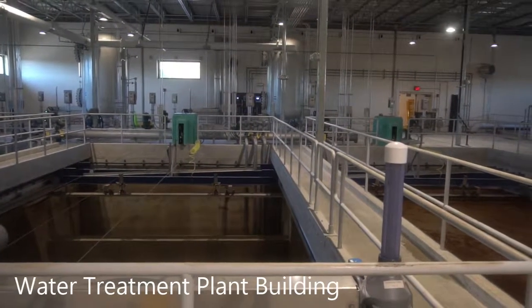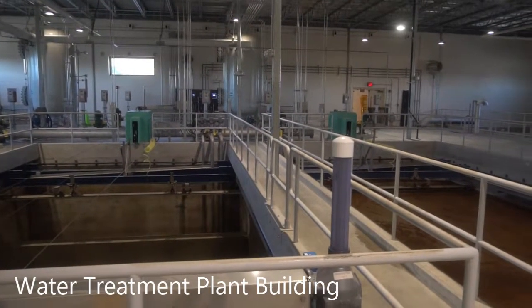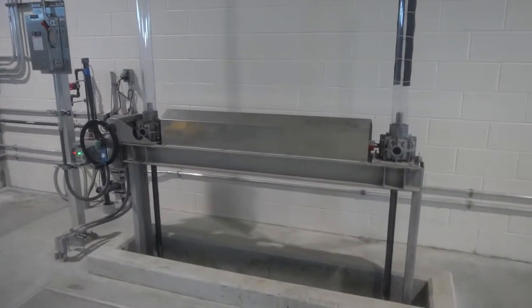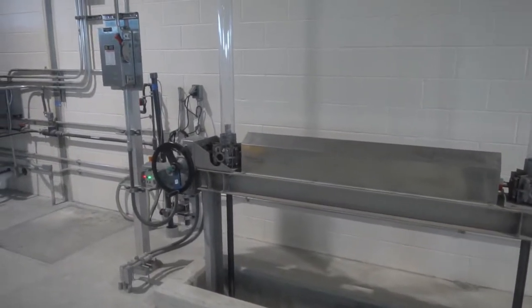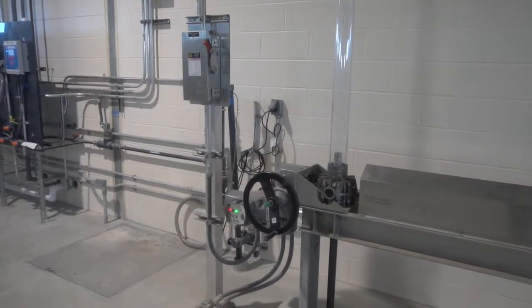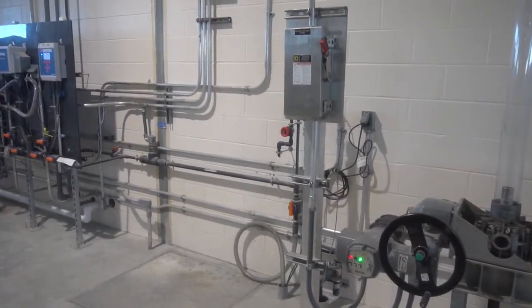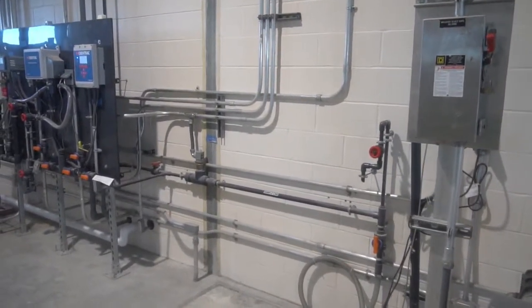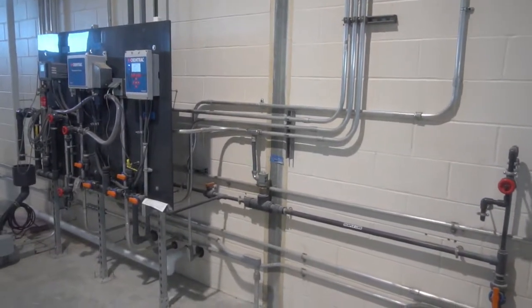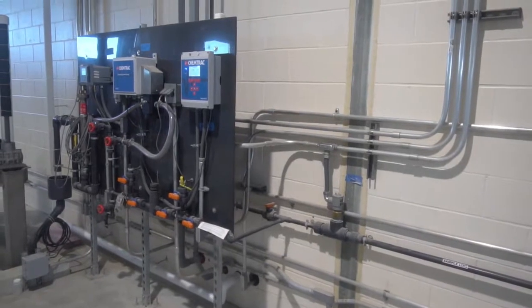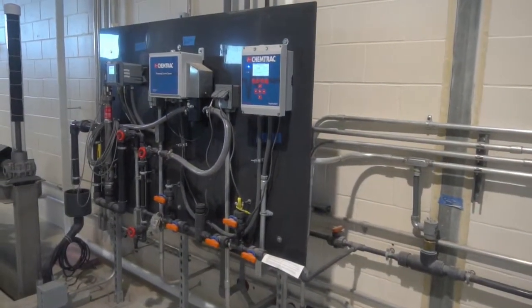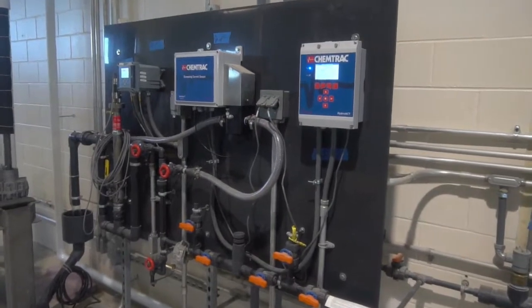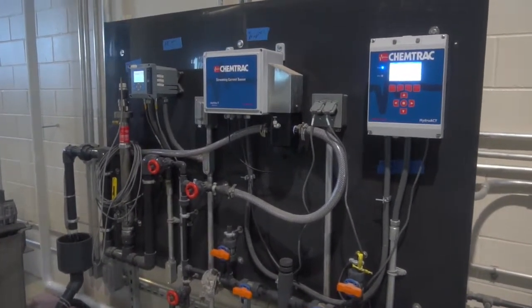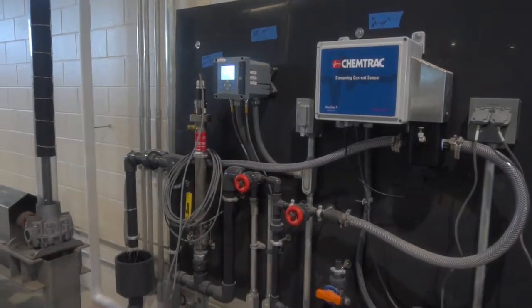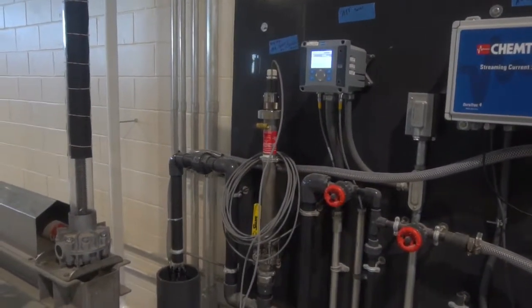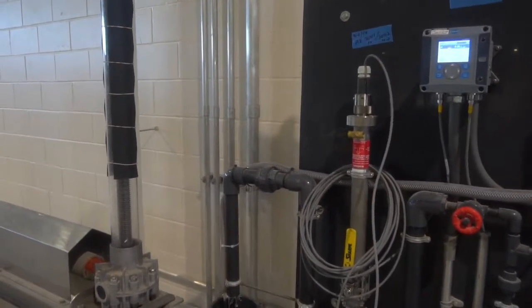We are now in the new water treatment plant facility. We installed 2 transmission lines from that low lift station which you saw previously. And they enter the building here. Paired with that equipment, we have process control equipment where we monitor the coagulation process and we monitor pH and temperature as well. At the advice of science experts and with Department of Health approval, we did substitute inline static mixers for rapid mixing.